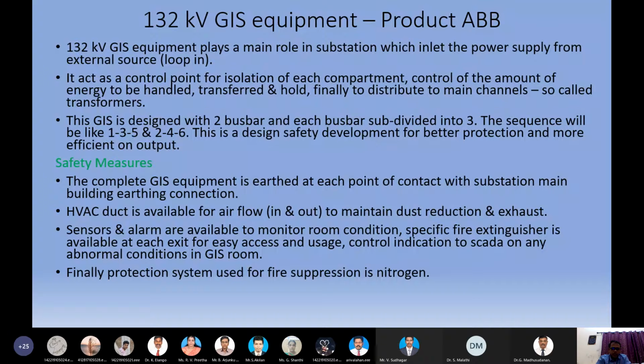The fire extinguishers are in each exit, as I said, and the control indication goes to SCADA on any abnormal condition in the GIS room. If the temperature is off, or there are any leakages, flashovers, or any other abnormal conditions, they will be indicated with the motion sensors in SCADA. This SCADA communication is intimated to the headquarters, so once it has been sensed, they send an emergency team and the maintenance team to identify what has gone wrong.